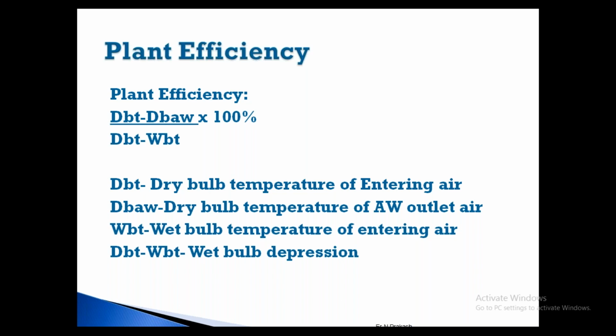So check the outside dry bulb and the dry bulb after the air washer; these two, divided by the dry bulb minus wet bulb. If you take the readings and check, you can see the plant efficiency. If your plant efficiency is lower, say 80% or 70%, then the dry bulb temperature you achieve will not be close to the wet bulb temperature. It will be higher. When outside is 43 and 24, you should be able to achieve 24 and 25. If you are achieving 30 and 24, or 32 and 24, the air you send may not be sufficient. You will be wasting the power and will not achieve the result because of the poor spray. There will be a number of reasons.